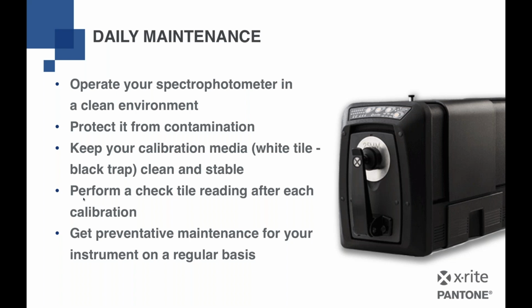What you see on the image here is a Color Eye 7800, our benchtop sphere instrument. We do have a vertical stand for that instrument so that no product or material could actually drop into that sphere, into the aperture of that instrument. Of course, as we learned just a minute ago, you should keep your calibration media, the white tile and the black trap, and that green check tile clean and stable. And of course, you should perform that check tile reading after each calibration, which is an automatic function you can enable in our software. And of course, we recommend you get preventative maintenance for your instrument on a regular basis. Now, for some of you, this might already be common sense. For some of you, it might not.